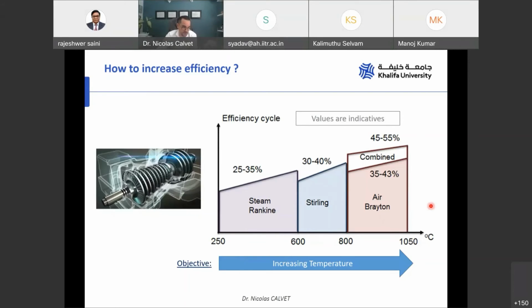For that, we need to reach high temperatures: for supercritical CO2 right now we are around 715°C, but for air Brayton we are talking about 800 to 1000 degrees Celsius. In this range of temperature, molten salt cannot be used because nitrate salts above 600°C are degraded. And if we consider other types of salt, for example chloride, we have a big issue of corrosion at this temperature level. Many laboratories are working on chloride, for example funded by the US Department of Energy, but personally I don't think chloride will be an option in the future. So we need to find other solutions to store heat at very high temperature in order to use this Brayton cycle, combine it with a steam cycle, and reach more than 50% conversion from heat to electricity.